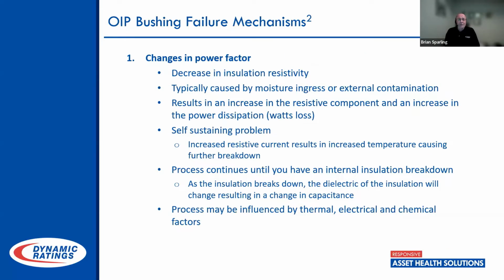So what makes a bushing fail? Well, it's the insulation system inside the bushing, which is totally sealed away from the rest of the transformer itself. The oil in the bushing should not be mixing with the oil in the main tank. Basically there's a condenser inside the bushing, where foil and paper is wrapped around the conductor as the lead passes through it. And we heard before that moisture ingress is one of the prime causes of insulation failure. This is understood, because leaks through gaskets at the top of the bushing are one of the favorite spots where moisture begins to come in.